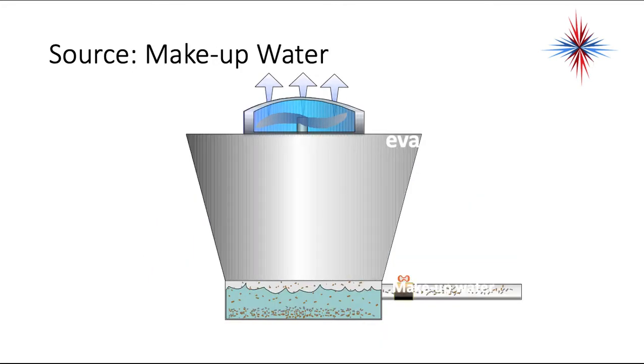Another source of contaminants is the make-up water. With cooling towers, we need to regularly make up the water that evaporates off because we deal with evaporative cooling. The make-up water brings a lot of contaminants into the system. Down at the bottom you'll see those as sediments — the minerals that are part of the make-up water will not evaporate out and will become part of the entire system.